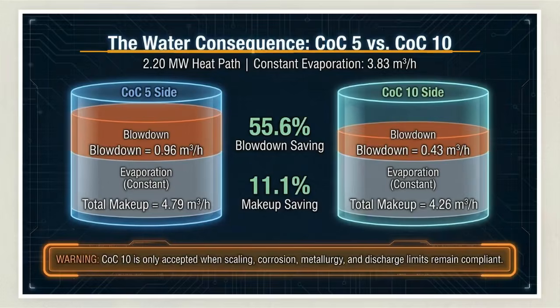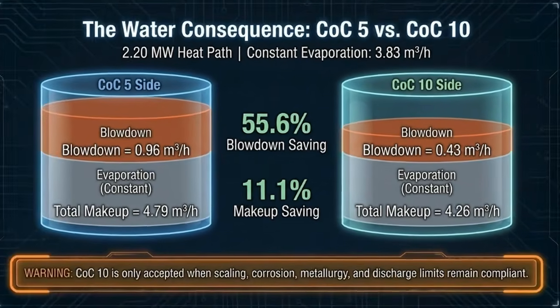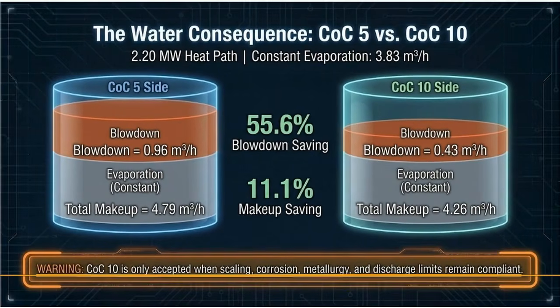This graphic illustrates running a system at 5 cycles of concentration versus 10. Doubling to COC 10 results in a 55.6% reduction in blowdown water, cutting waste. But achieving these savings safely demands automated filtration and metallurgy compliance. Without precise chemical management, high cycles lead to catastrophic scaling and corrosion.